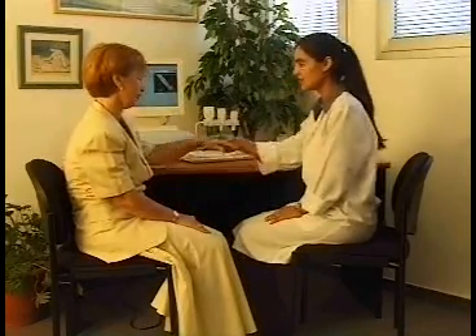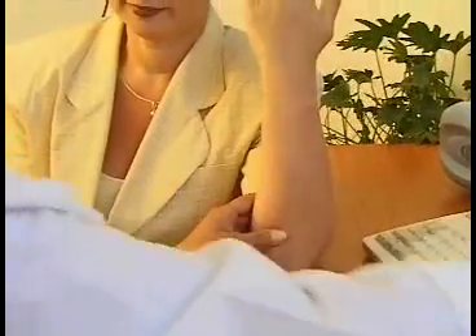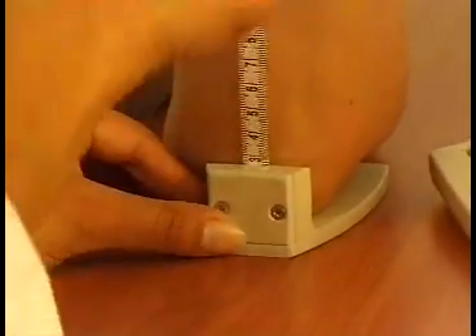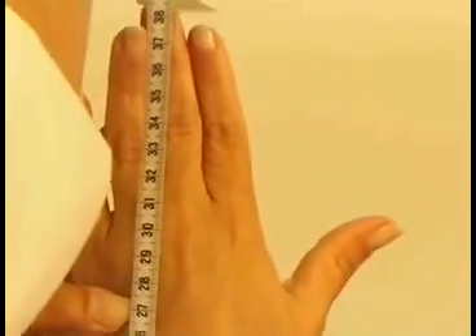To measure the radius, the subject should be in a sitting position opposite the operator and next to a standard desk. Use the measurement gauge to determine the position to make the measurement. Place the subject's non-dominant arm on the gauge platform. The elbow should be positioned so that the arm is perpendicular to the platform and the palmar side of the palm is facing the subject.